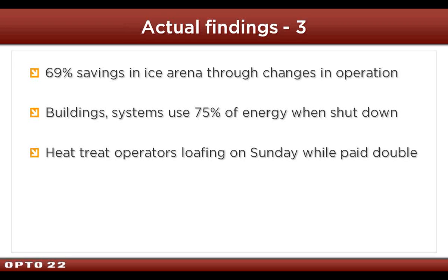So we went into an ice arena. They had previously had some big capital projects, spent a lot of money, and cut about 50% off their operating costs. About 3 or 4 years later, we went back in there, still had all the capital, so that wasn't the problem, but their costs were back up to where they had been before. The changes by outside contractors and staff over, I think it was about 8 years, had destroyed all the savings.